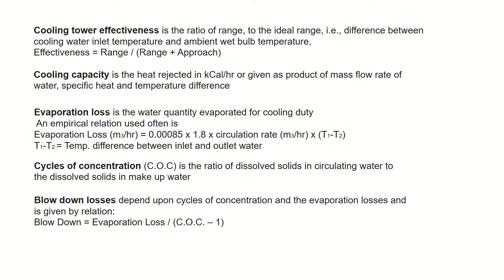Before measuring the performance of a cooling tower, I will explain some important terms. The first is cooling tower effectiveness, which is the ratio of range to the ideal range — that means the difference between the cooling water inlet temperature and the ambient wet bulb temperature. Effectiveness is calculated using the formula: effectiveness equals range divided by (range plus approach).